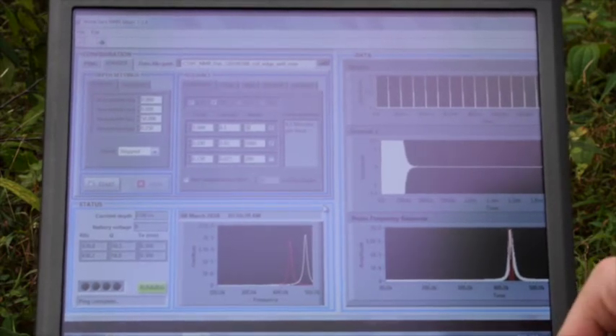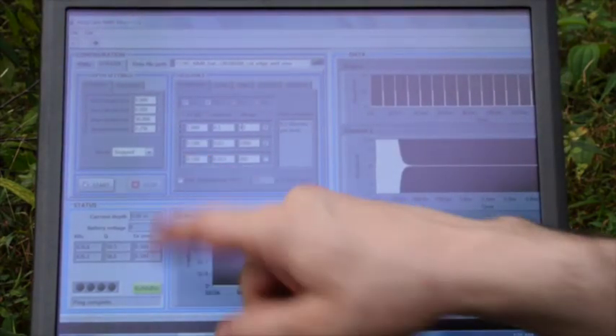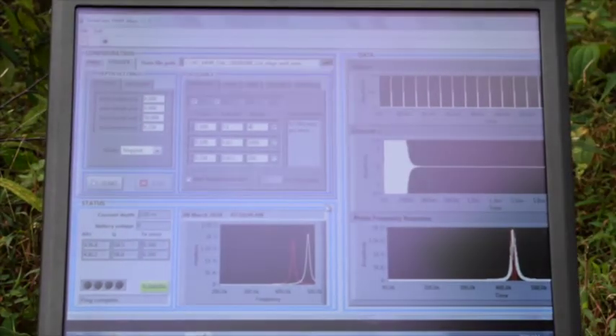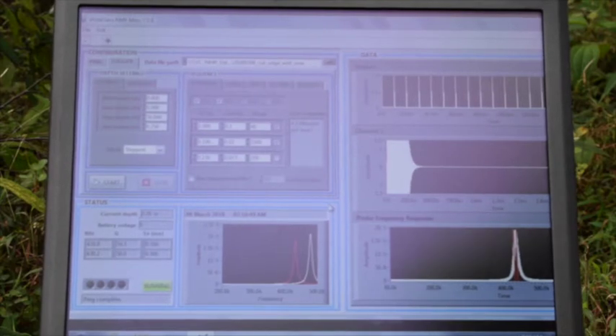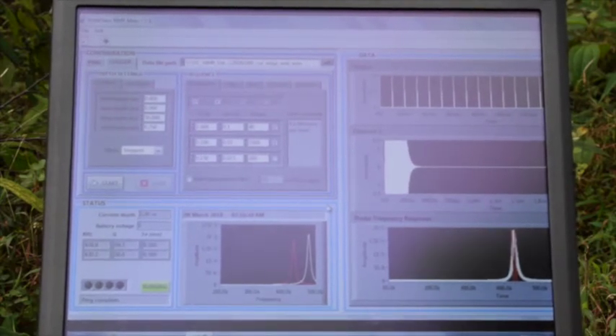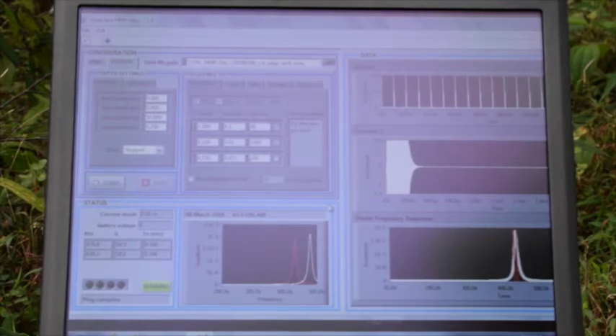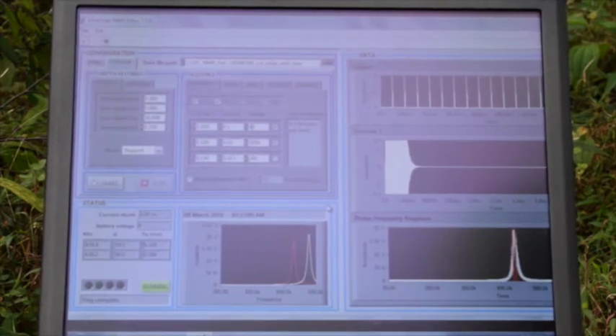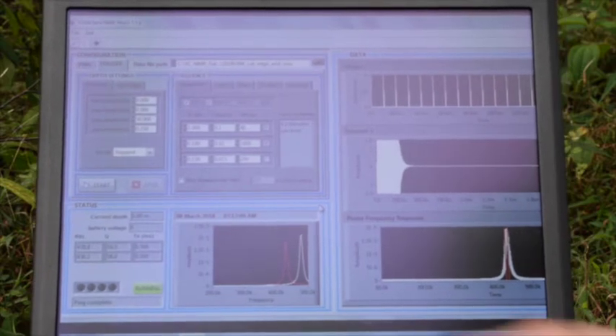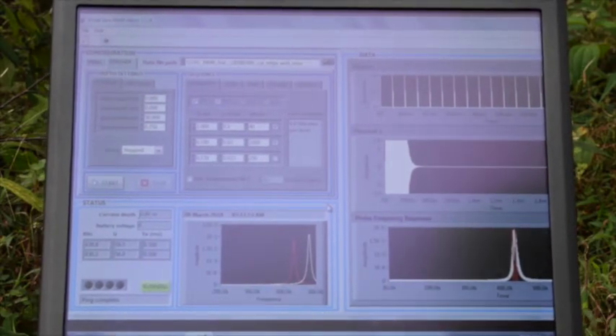Typically, I increase the number of averages on the long wait time. So the top TR is your recovery time, and the long one is 1 second. These are for longer water that's going to be in larger pores or bulk water, so I usually increase the number of averages on that. It makes it take a little bit longer, but I think you get better data for those longer relaxation times. And if you have a reason to do something different, then we probably would have discussed it before. Aside from that, that's a pretty reasonable place to start with settings.